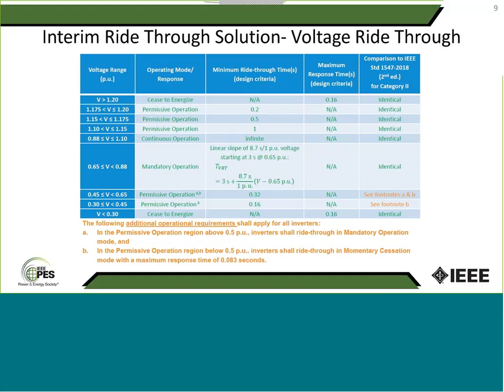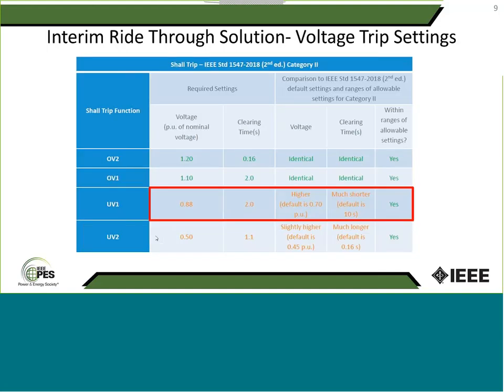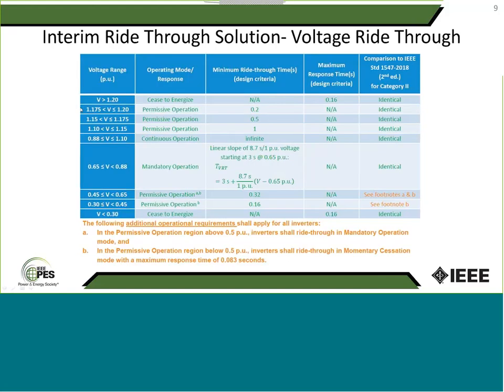So this is basically the slide showing the ride-through capability that we mandated for Massachusetts. We picked the Category 2 ride-through capability table from 1547 because the settings on this slide are actually within the range of Category 2 trip points, okay? We couldn't do Category 3 because Category 3 did not have these trip settings, but Category 2 did. And so we were very comfortable with Category 2 requirements.